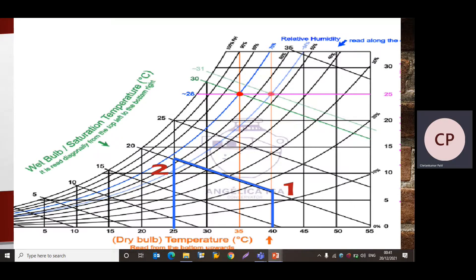For point 2, the dry bulb temperature is 25 degree Celsius, so we draw a vertical line from 25°C. The wet bulb or saturation temperatures — 10, 15, 20, 25 — are shown on the chart, and inclined lines from those temperatures indicate wet bulb temperature lines. We take the inclined line from 20 degree Celsius and find its intersection with the vertical line from 25 degree Celsius. That intersection gives us point 2. We then join point 1 and point 2.